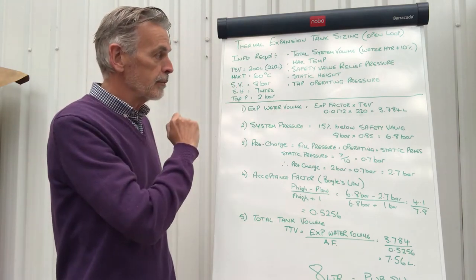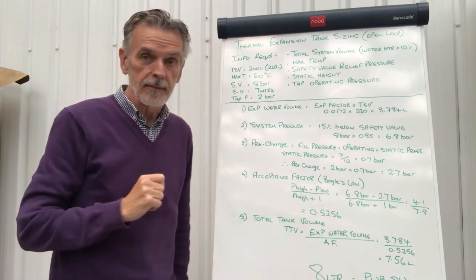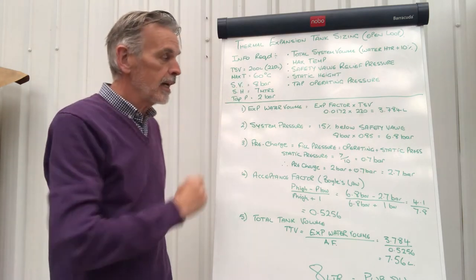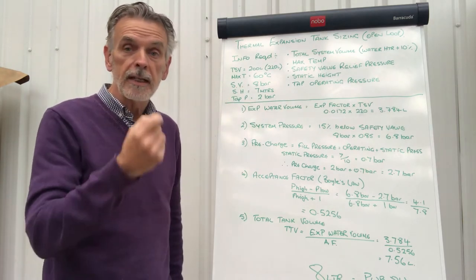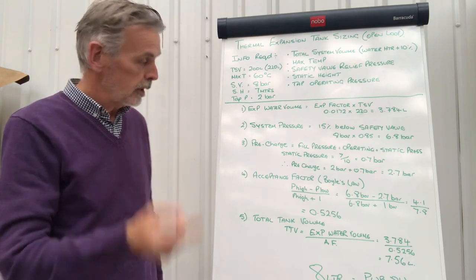The safety valve is set at 8 bar. The static height is 7 metres, and we have a tap operating pressure required at that point of 7 metres at 2 bar.